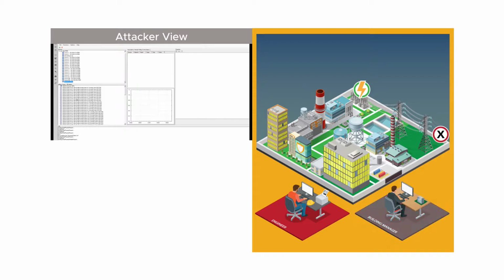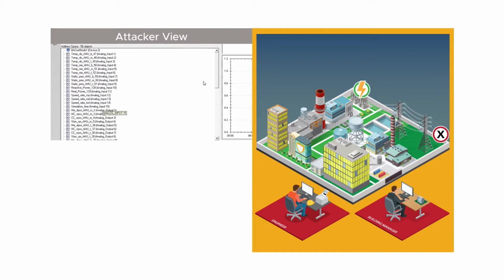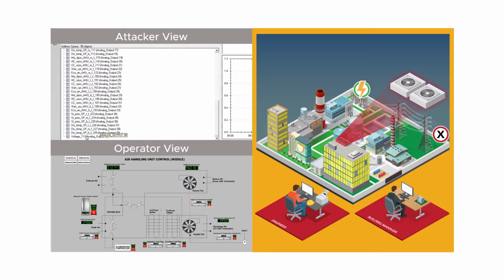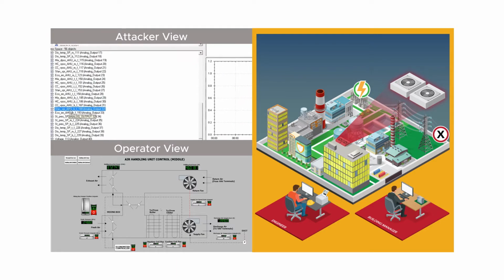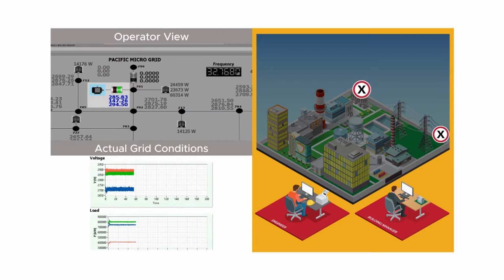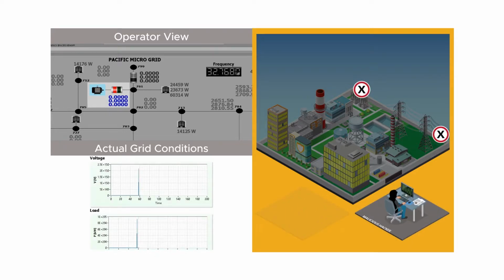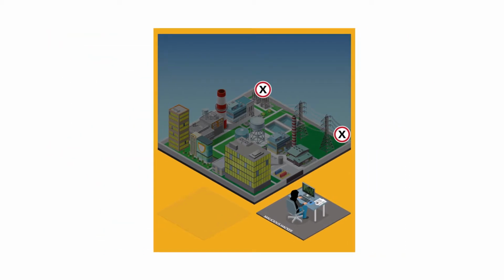Now our attacker has become Joe Schmo, using the victim's credentials to remote desktop into the building control system. This lateral access to the engineering workstation allows our adversary to choose the operational devices and systems he wants to attack in campus buildings. In this case, he accesses controllers that manage the air handling fans. Changing the speed to slow the fans causes a downward spike in power, which will cause the generator to trip off to protect itself. Now, the campus is completely without power. The attacker's objectives have been met.